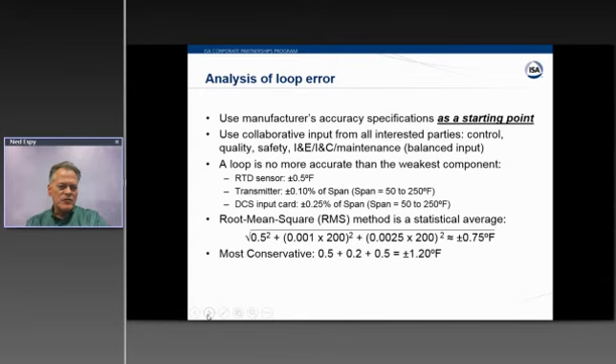One method in metrology is to use an RMS statistical average. So if you square each value, and in this example, I'm changing everything to degrees F, if you square each variable, add them together and take the square root, instead of a half a degree, which is the weakest link here, the other two elements, the transmitter and DCS input card, would add an additional quarter of a degree uncertainty or error to the measurement. So maybe that's the best you could expect out of this loop. Maybe you'll set a pass-fail on the loop of 1 degree. Just give yourself a little breathing room.